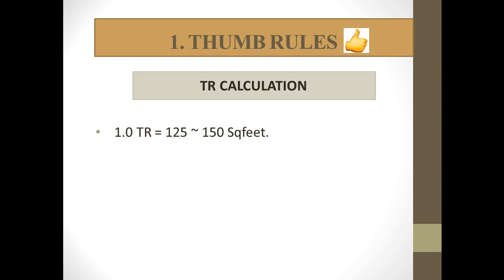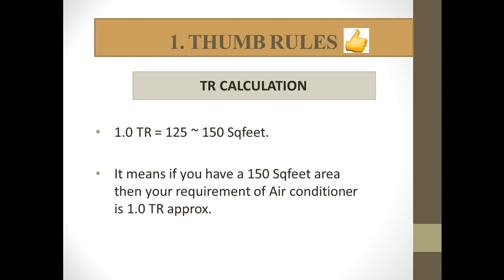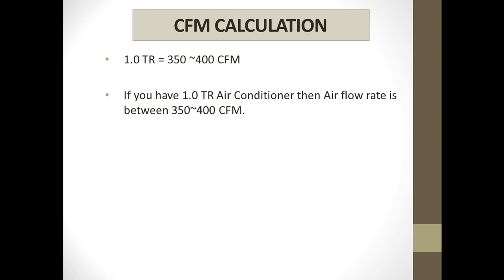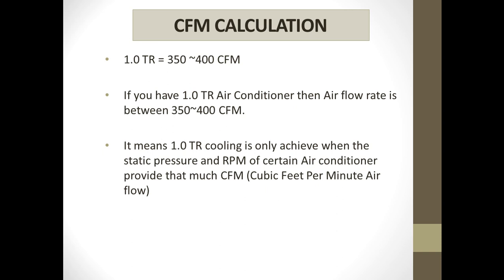The first topic is thumb rules. For tonnage calculation: 1 TR is equal to 125 to 150 square feet — meaning if you have a 150 square feet area, your air conditioner requirement is approximately 1 TR. For CFM calculation: 1 TR is equal to 350 to 400 CFM, meaning if you have a 1 TR air conditioner, the air flow rate is between 350 to 400 CFM. 1 TR cooling is achieved when the static pressure and RPM of the fan provide that much CFM (cubic feet per minute) airflow.